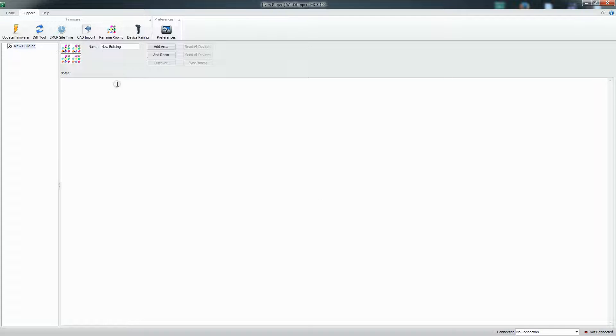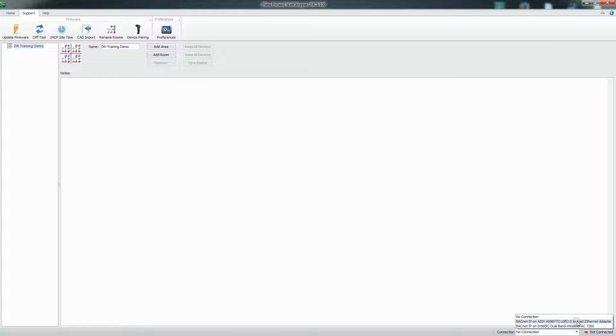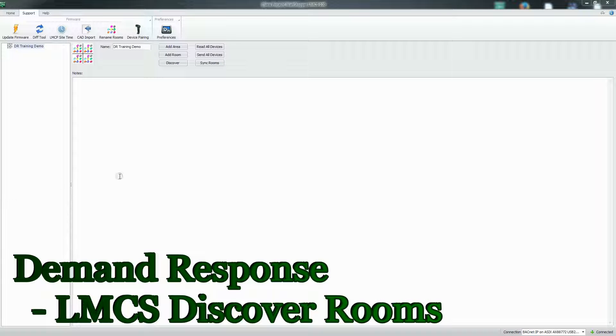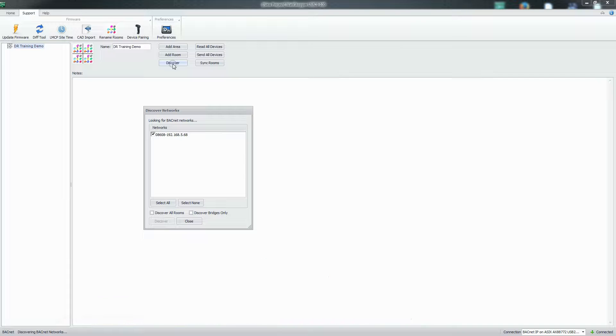I'm going to rename this file to 'DR Training Demo' and select my connection. I'm connected to a USB Fast Ethernet adapter, which connects directly to the NB switch that has my segment manager and NB router on the same IP structure. Now that I've connected, you can see the little green connection LED and the Discover option is highlighted. With our connection established, we can go ahead and discover the rooms. Notice that the router immediately shows under available networks with its MSTP network number, IP address, device ID, and description.